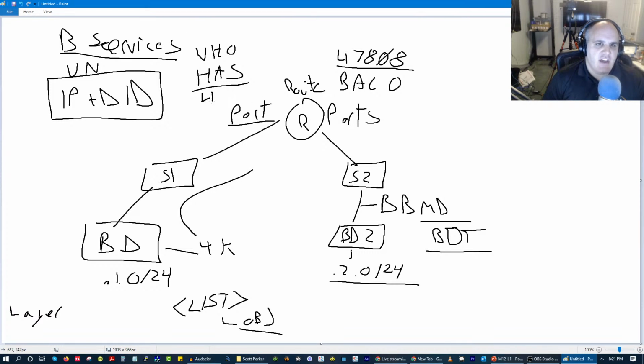Anyways, though, you're going to come to some job sites that have one set up as port 47808 and another set up as like 47809. And this is where routing needs to take place. And in your routers, you will say, okay, we need to route to this port as well as this IP address. So it's a very simple fix, but if you're not cognizant of it and you go to troubleshoot and you're like, I'm pinging 47808, but I'm not getting any traffic, that would be why. And it's just a matter of realizing that you have routes and things like that.